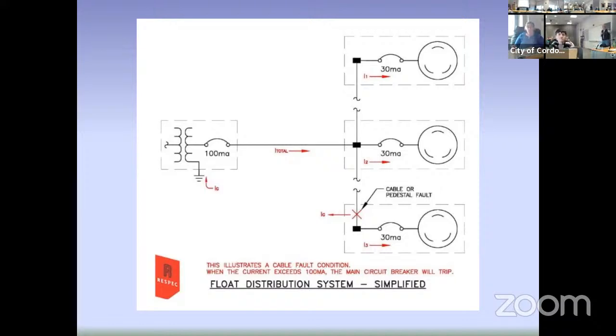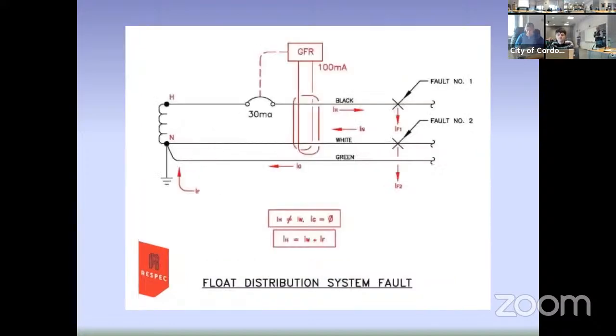So this is that other condition where we're affecting the feeder circuit breaker. This is where we would have a fault on the cable. That should not affect the pedestal breakers, but it will affect the one in the main distribution panel. And this is illustrating that in more detail, showing the fault going into the water and back up, and it will trip.